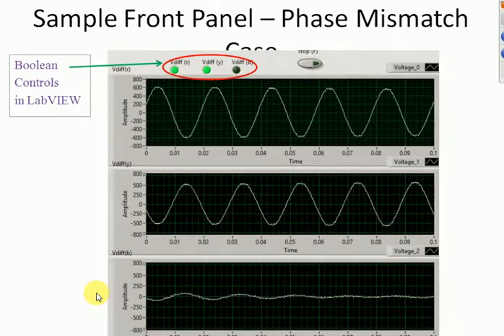In case there's a phase mismatch, the voltages are not equal and you can see these indicators glowing, meaning this is not the time to synchronize. There is a need for the phase sequence to be identical on both the generator side and the grid side, and the voltage difference should be small. Only then can you synchronize it. All of that is displayed here.